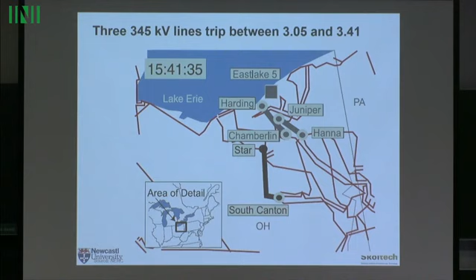What happens when a line trips? Here, the first one, whatever it was, one of the lines tripped. As you can see, this is the loading on each of the lines. When one line tripped, the loading on the other lines increased because the power had to be carried by some other lines. Then the next line tripped, again power loading increased, and then the next one tripped, and again power loading increased, and you had this cascading effect, one after the next tripping. Not only do power loads get redistributed, but voltage drops because the lines are heavily loaded. Ohm's law: voltage is current times impedance. Current increases, which means voltage drop increases.